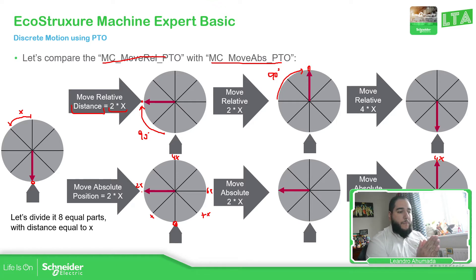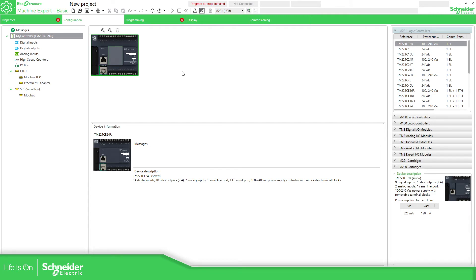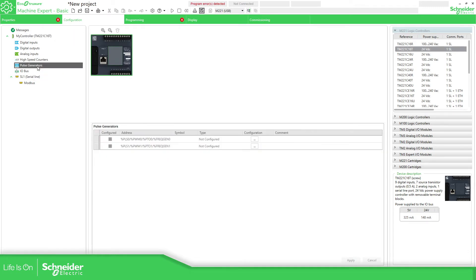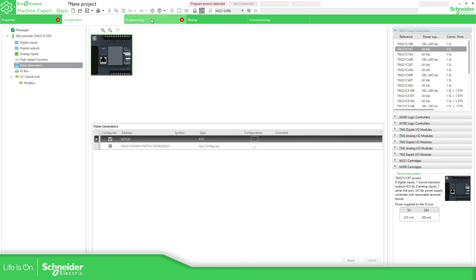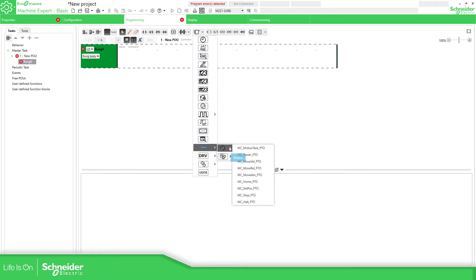Now I'm going to show you the behaviors of these two. First, you need to select the PLC that has the PTO functionality. This one is R — from relay output — it doesn't have that, so I'm going to drag and drop the version with transistor output. Here in the pulse generator, you just need to configure the PTO. I've already explained this part in another video, so I'm not going to go further on this. On the programming side, we just go to Functions, PTO, PTO Motions, and you can find the Move Relative and Move Absolute there.